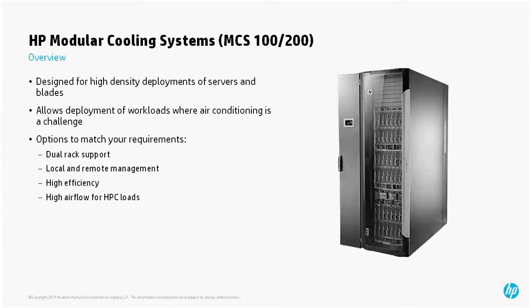What you see here is the 100, and you'll see it's a rack that looks just like our intelligent racks. It's basically the same rack, only there's a layer of plexiglass in there so there's no air in or out of it. Cold air comes in the front, goes out the back, and goes through that unit you see next to the rack, where you've got the cold water in, the hot water out, and you're running air through some coils with a bunch of fans, keeping that air moving, circulating, and cold.